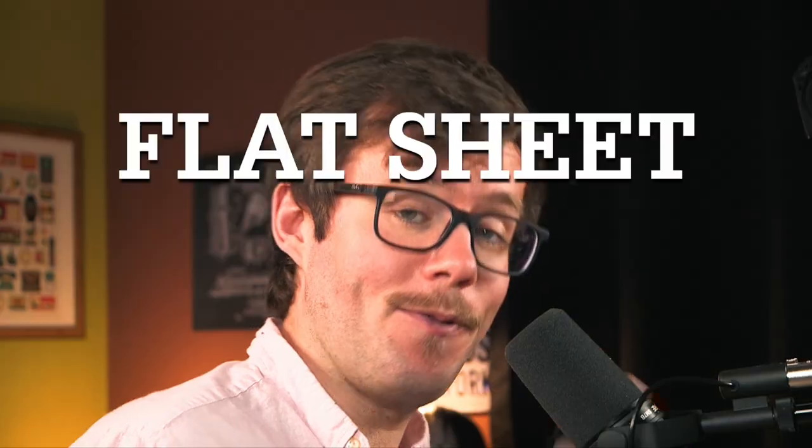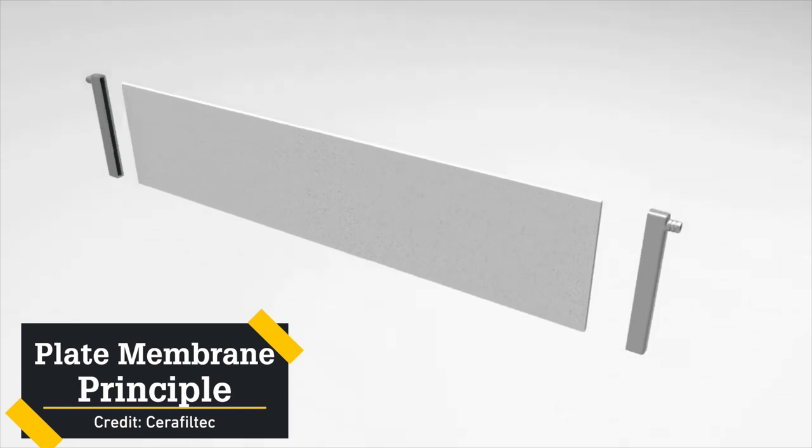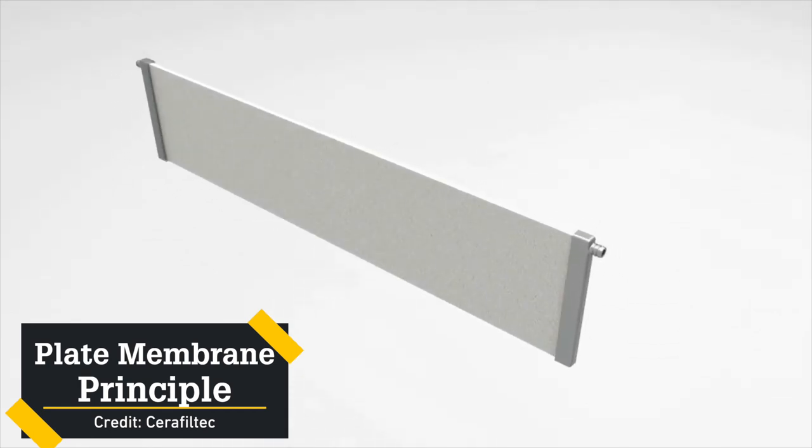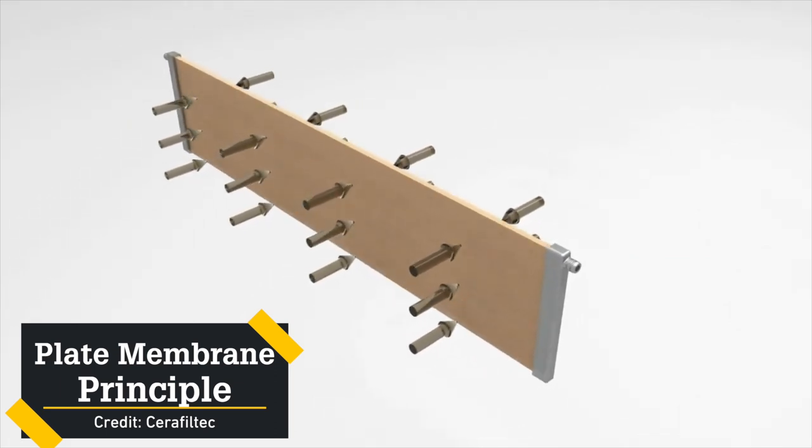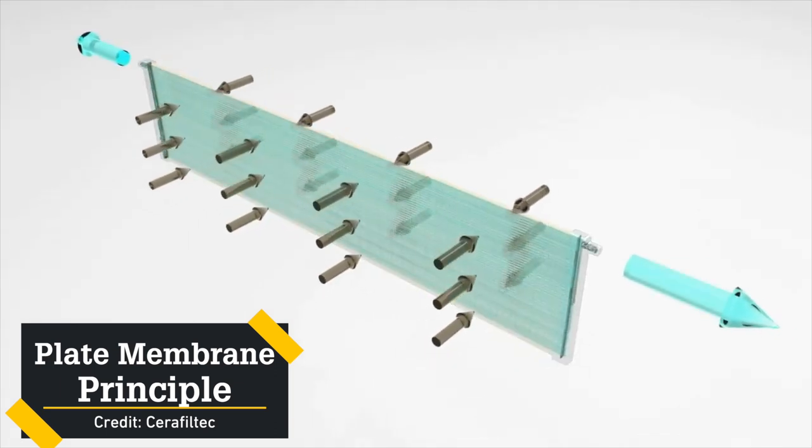Flat sheet membranes, sometimes called plate and frame membranes, are built around a series of flat sheet membranes and support plates. The water to be treated passes between the membranes and adjacent assemblies, with the plate supporting the membrane and providing a channel for permeate to flow out. This design enables straightforward modularity, allows low footprints, and optimizes hydraulic design — though it is said to be subject to clogging and harder to backwash.